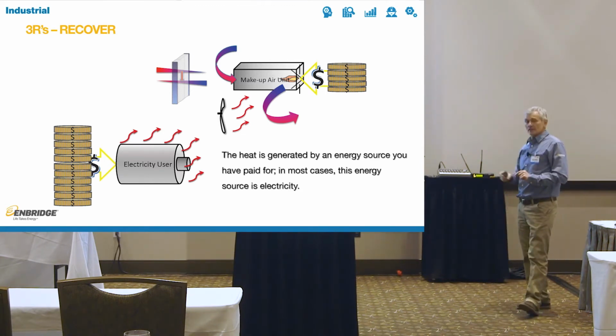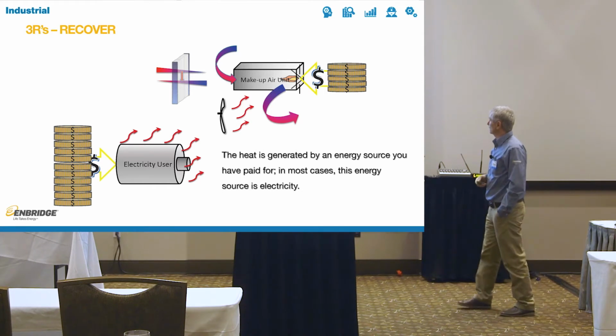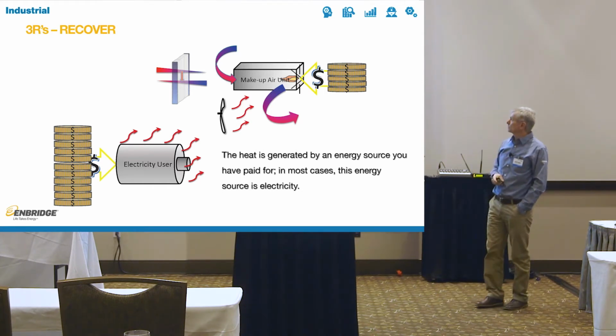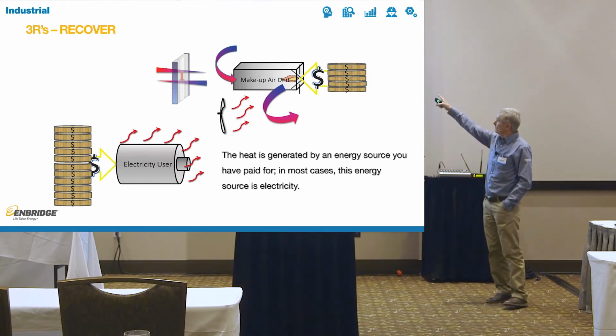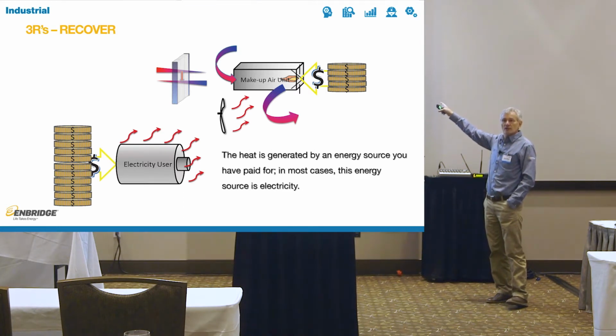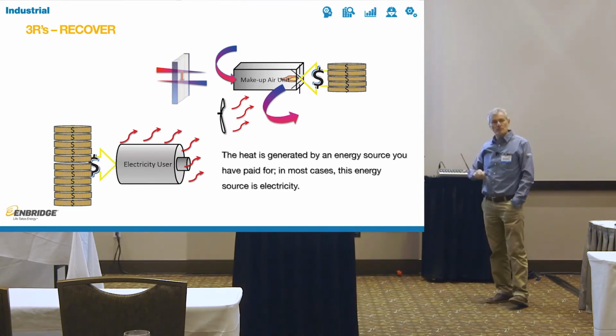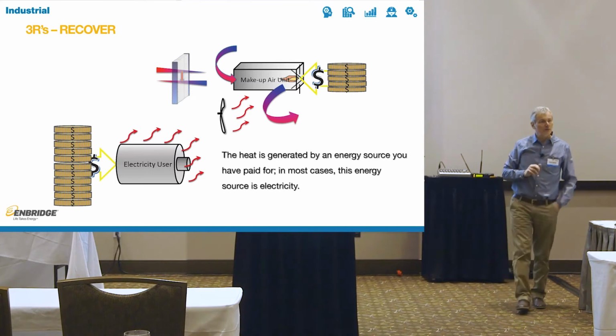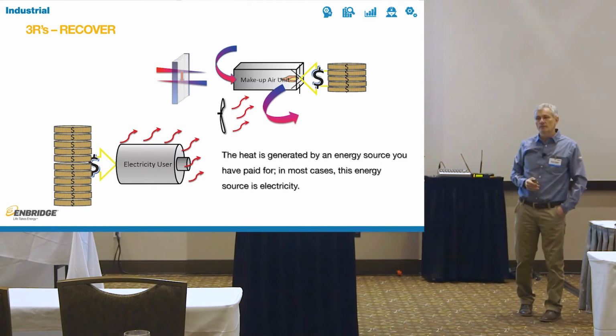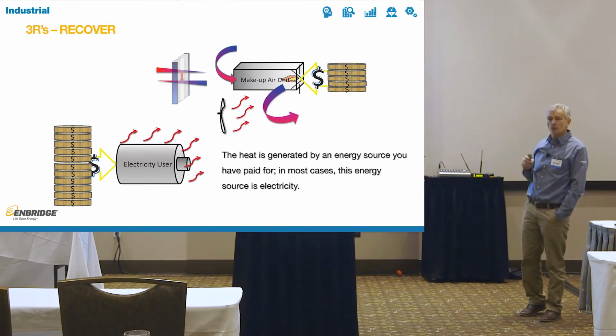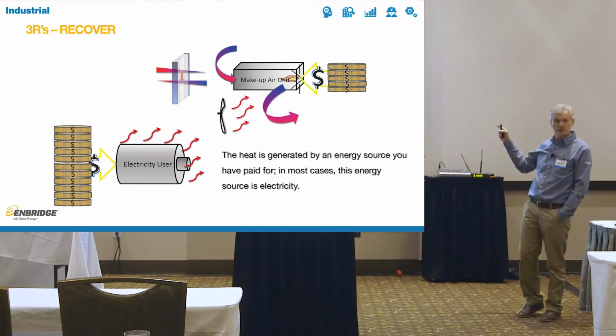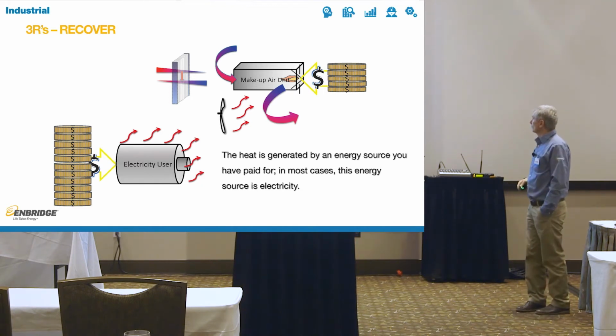So to use some of that heat, let's say we can take some of that heat, put it through some sort of heat exchanger, preheat the air before it goes into the makeup air unit, and you reduce the amount of money you're going to spend on your makeup air heating because the delta T will be smaller. But that can be a fairly complex thing to do. It's possible. For some, it's very doable. It's still within a 2-year project for most, but we can do better.